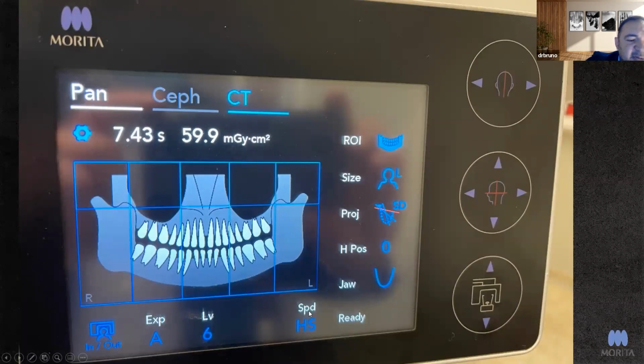So there are 2 different resolutions, right? You have the high-speed resolution and the HD resolution. The difference between the high speed and the high definition is always the acquisition time. Here on high speed, the panoramic is going to be 7.4 seconds. On the high definition, the panoramic is going to be 15 seconds. If you're just using the panoramic image for scouting the area of interest, then you should use high speed. If you're using the panoramic image for diagnosis, meaning that's the primary reason why you are imaging the patient, you should be using the high definition one.